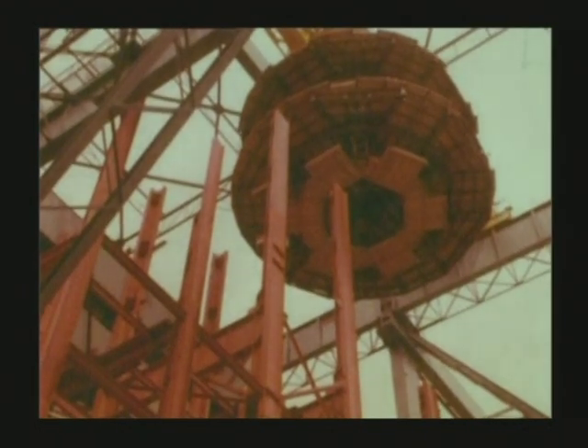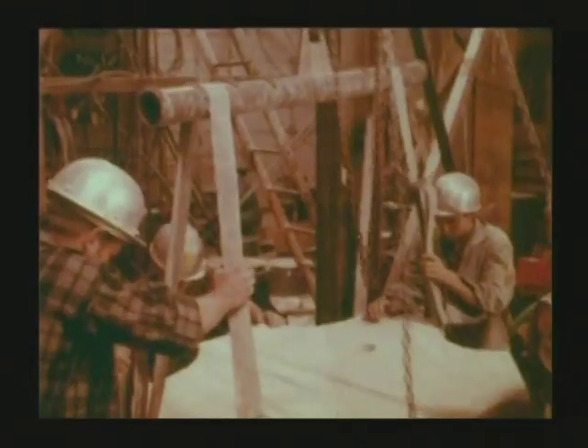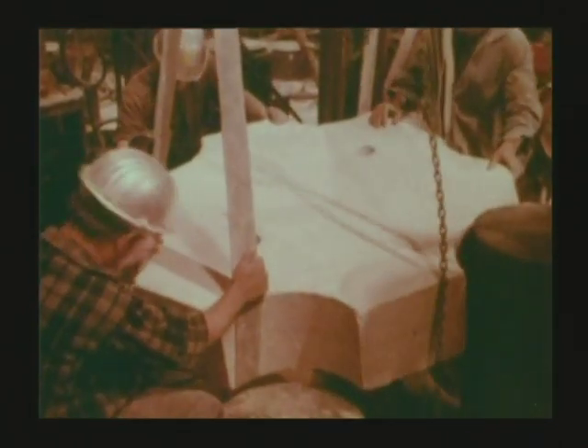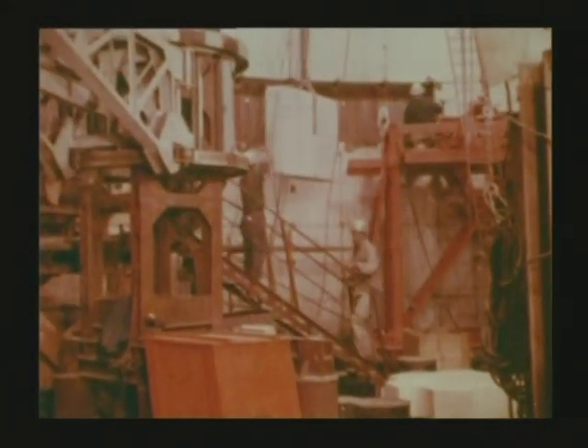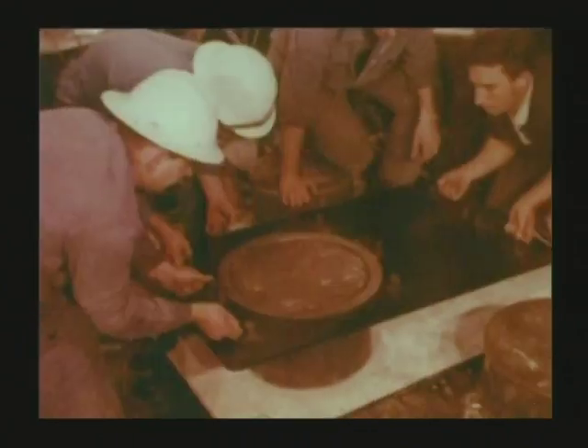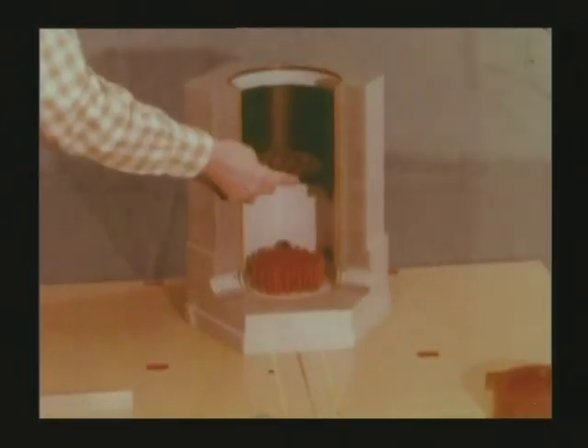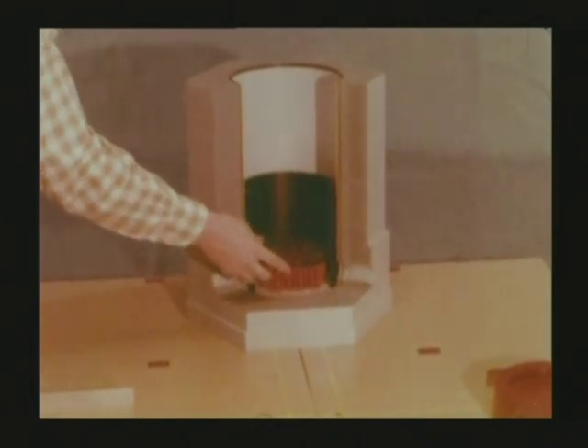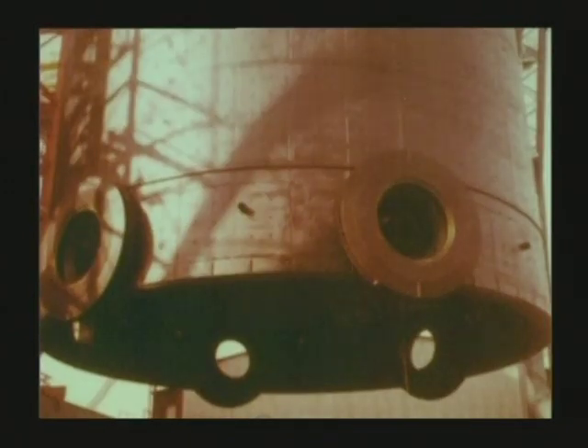While the concrete of the vessel is being cast, a working platform is set up within the enclosure to allow the placing of the heat insulation material. This insulation consists of thick slabs of pumice concrete. The slabs are fastened to the walls and floor of the vessel. The slabs are shielded for mechanical protection and to prevent pumice dust from being released into the primary system. The reactor vessel having reached this stage, it is possible to insert the core supporting structure. This 500-ton cylinder, consisting of cast steel segments bolted together, was assembled on the site like all the heavy components.